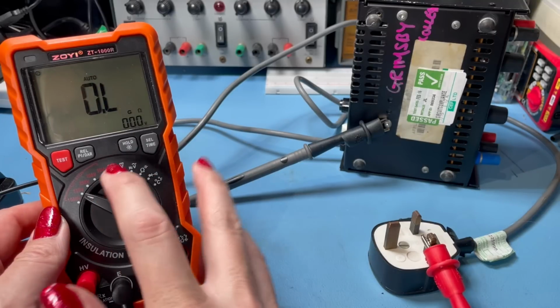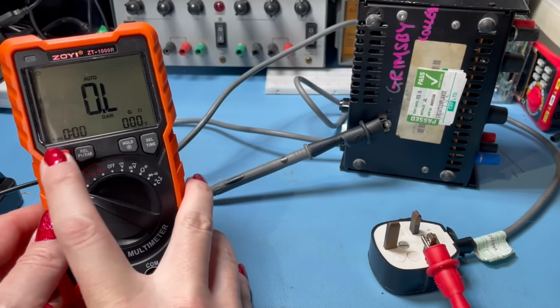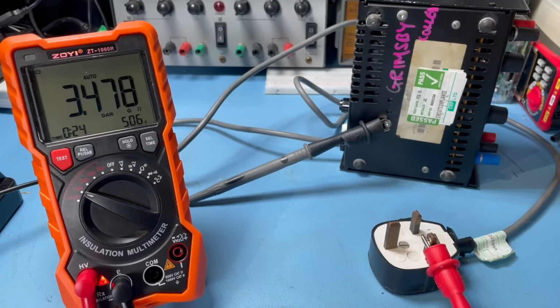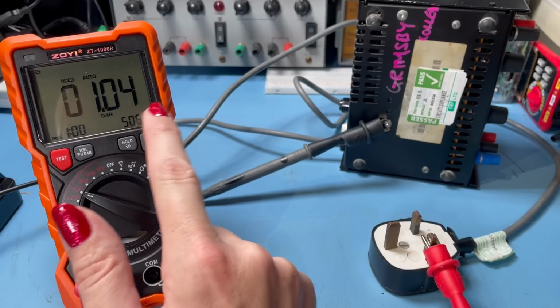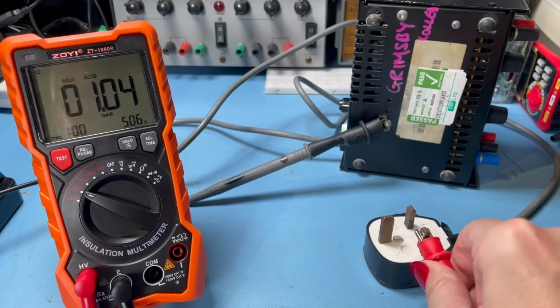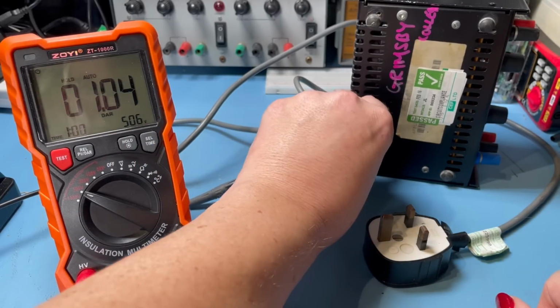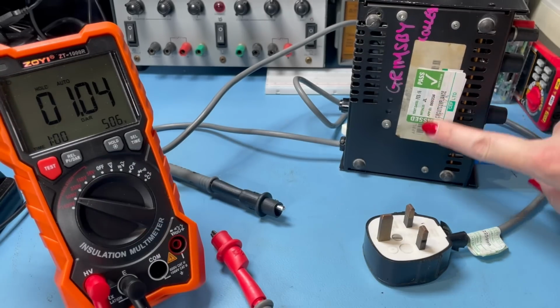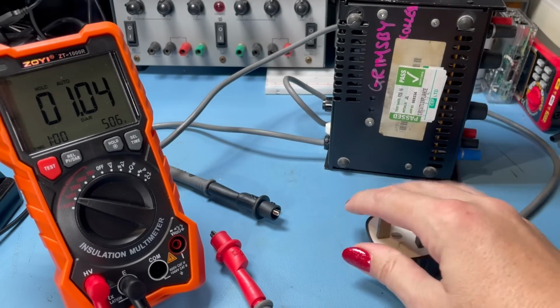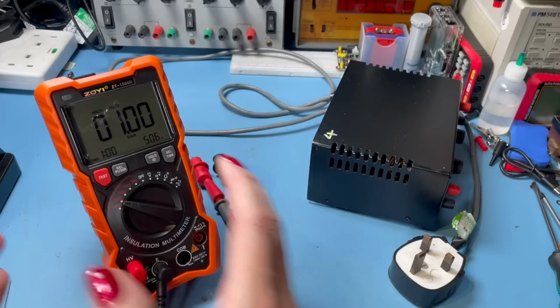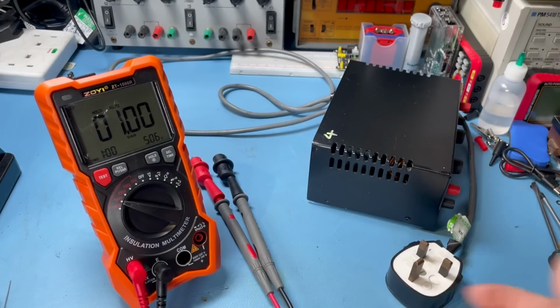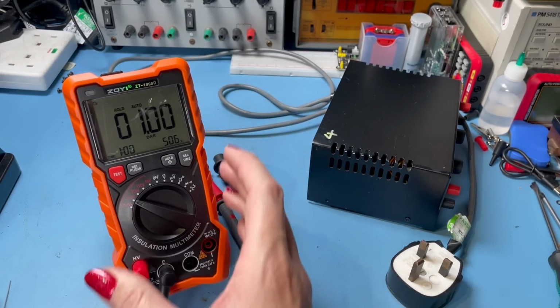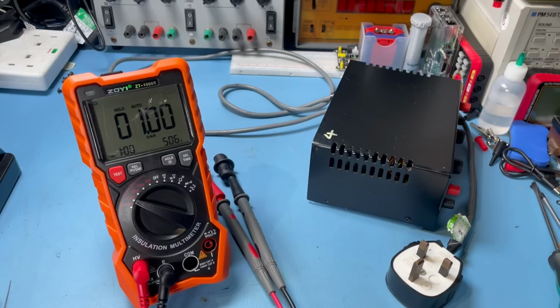Okay, same test again, 500 volts DAR. Let's test. There we go, we've got a DAR of 1.04. So in this case, I would say that insulation is fine, and indeed it did pass its last PAT test. I think it's due for another one. Again, if you were getting spurious readings on any of this, you could do your 10-minute PI test to give yourself a bit more of an in-depth indication about the insulation of this appliance.